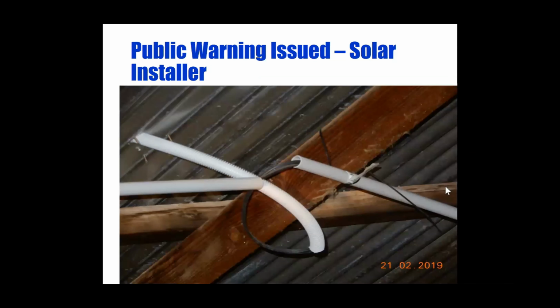This is a solar job that we found, and I've already shown this to a lot of solar installers. However, I think it's important that we show it to you guys because it's how we ended up giving out a public warning. This here is a solar, and for those of you that don't know, solar within the confines of a building has to be in heavy-duty conduit, and this is not. If a rodent or something is to walk along these timbers, it's going to start chewing on these. DC is a funny beast. It's going to start arcing and sparking, and then maybe catch fire. So this is not right.